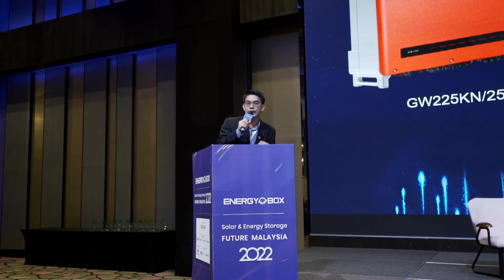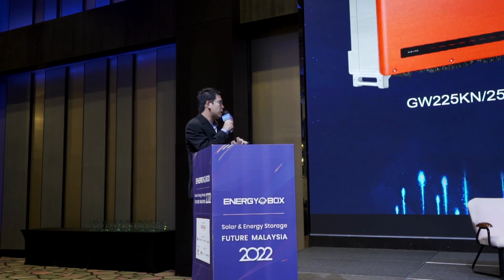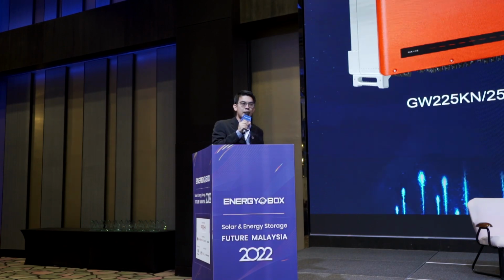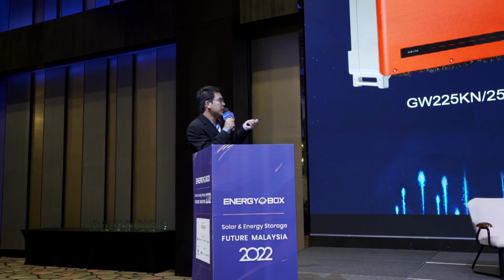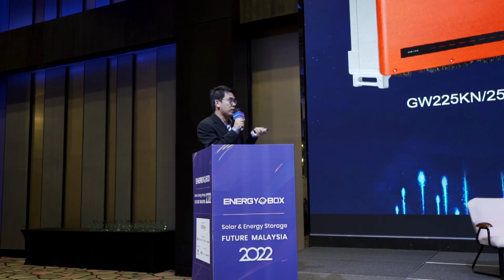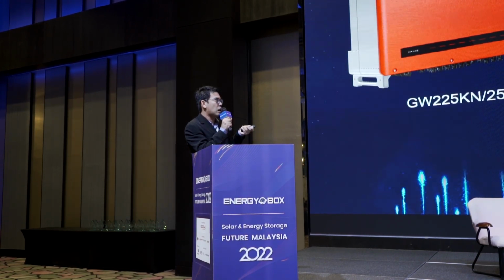So all our inverters are designed without fuse. It's a fuseless design, so we remove one of the main failure points in the system. But again, people will say you have three strings in one MPPT, how do you overcome this IEC? For that, we have a very smart DC switch to fulfill the fuse-free design. The DC switch will trip automatically when there's overcurrent and is also able to extinguish any arc that occurs within. So this is very important. And when everything recovers, it will connect back automatically.